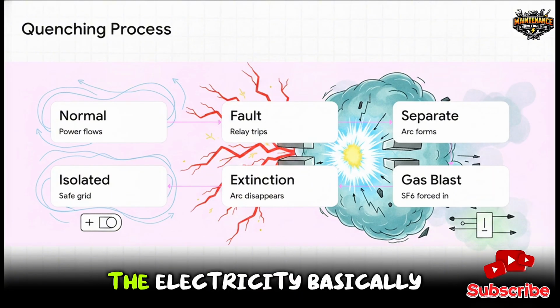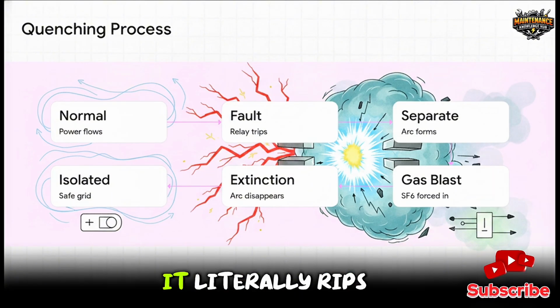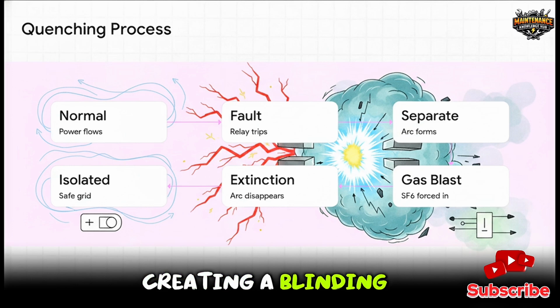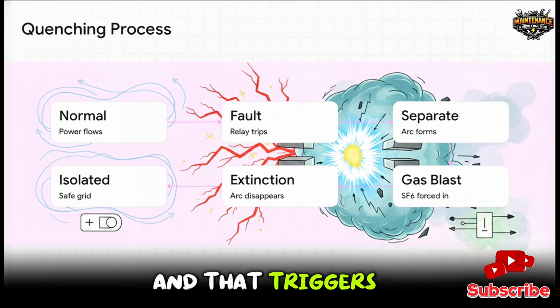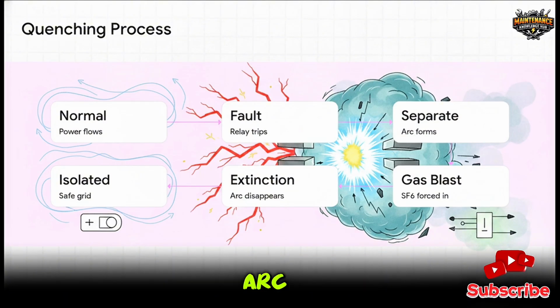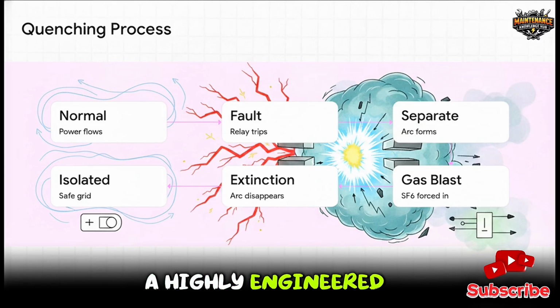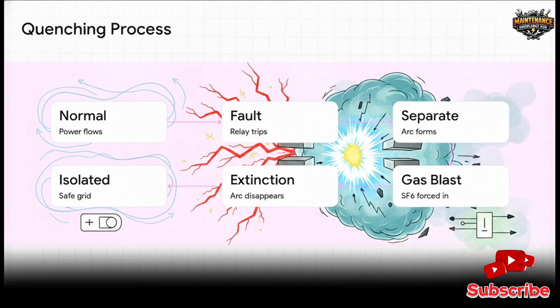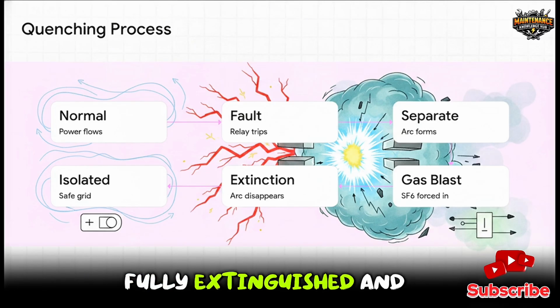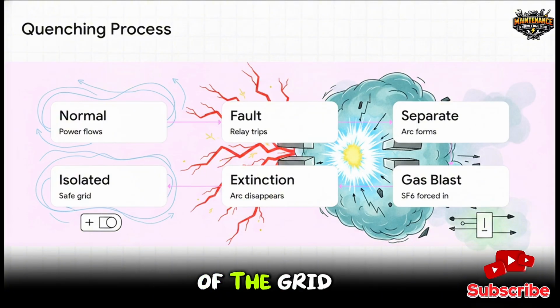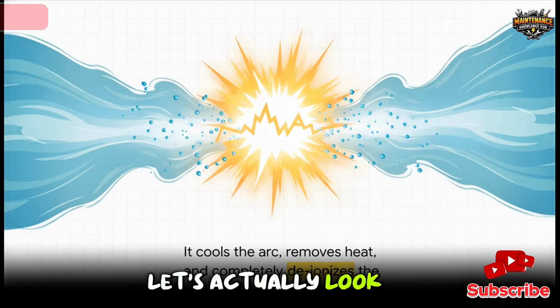Now, as they separate, the electricity basically refuses to stop. It literally rips through the gas, creating a blinding, superheated electric arc. And that triggers Step 4, the SF₆ gas blast. High-pressure gas is forced through that Teflon nozzle directly into the arc. It is essentially a highly engineered fire extinguisher for rogue electrons. By Step 5, the arc is fully extinguished, and in Step 6, the faulty section of the grid is safely isolated. Let's actually look a bit closer at the physics of that gas blast in Step 4, because honestly, it's fascinating. The blast doesn't just blow the arc out like a birthday candle.